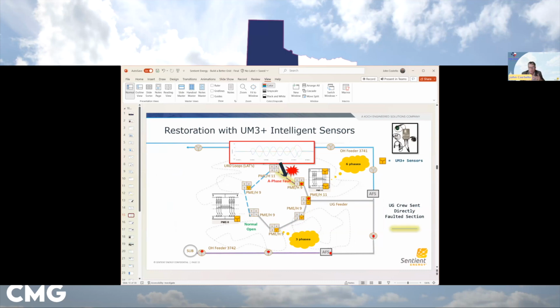Patrolling for faults can be problematic when the fault is somewhere between overhead and underground. So essentially you eliminate the overhead first, then start working through all the cabinets. This could be a multi-hour process, but if you know where the fault is and on which phase, you can go right to that area to address the issue and restore customers.